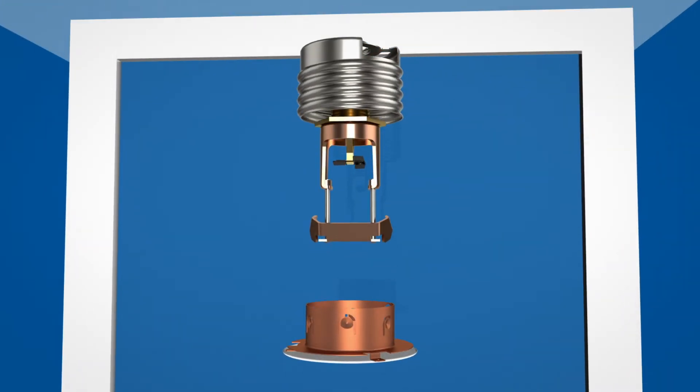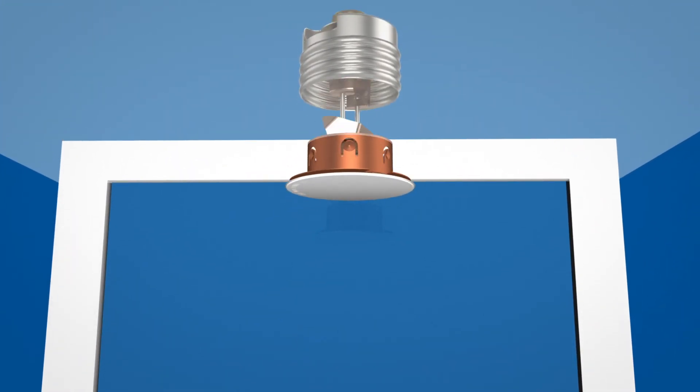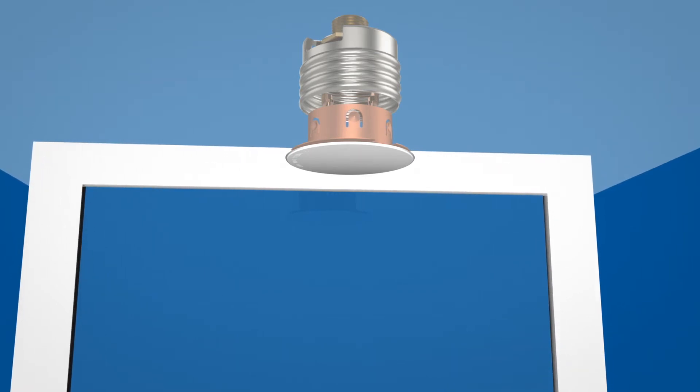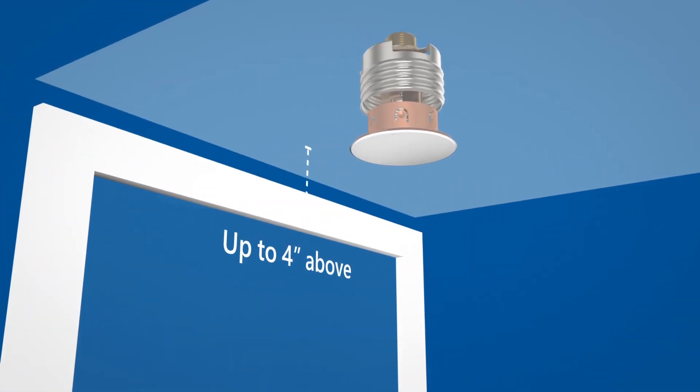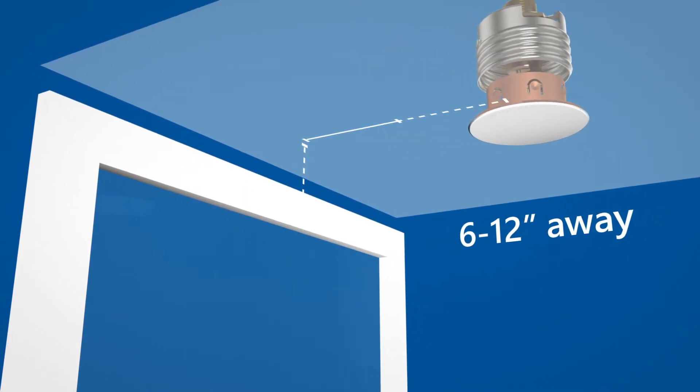Concealed window sprinklers are designed to be installed hidden within the ceiling and therefore are more aesthetically pleasing. They can be placed anywhere from flush to four inches above the top of the glass and six to twelve inches away from the glass.